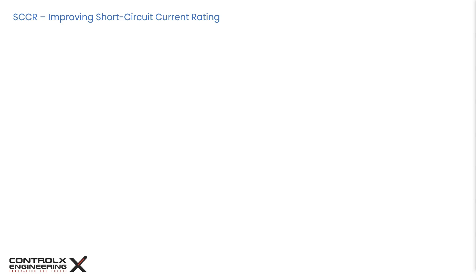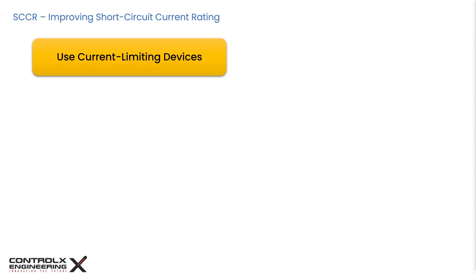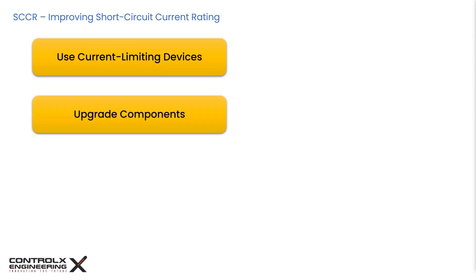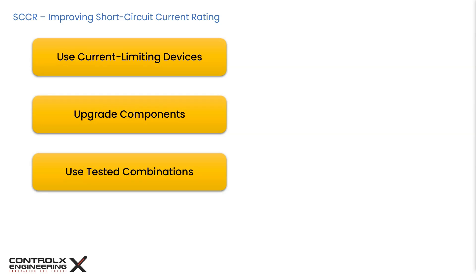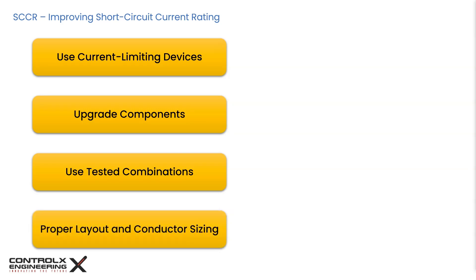There are several techniques to improve SCCR ratings. First, use current limiting devices — adding current limiting fuses or circuit breakers can reduce the fault current reaching downstream components, interrupting fault current in less than half a cycle. Second, upgrade components by replacing low-rated components with ones that have higher SCCR ratings. Third, use tested combinations — manufacturers sometimes provide tested combinations of components with a higher combined SCCR than individual parts, as seen in example two. Finally, proper layout and conductor sizing matters: minimizing conductor length and ensuring proper sizing reduces impedance, helping manage fault currents.